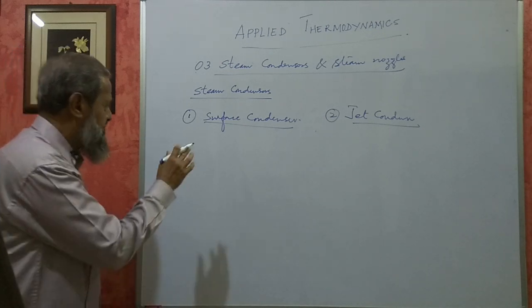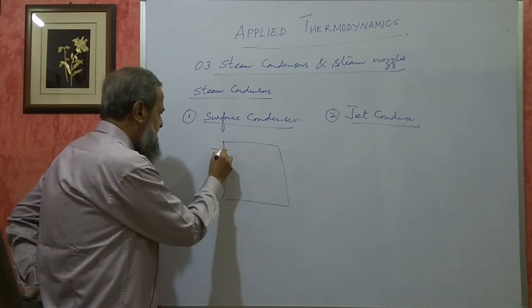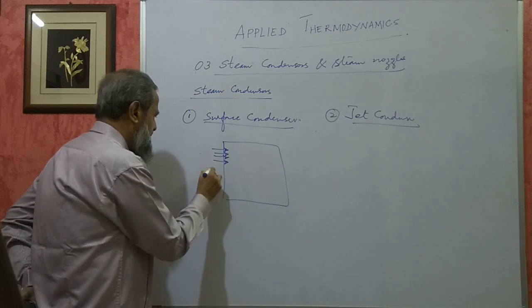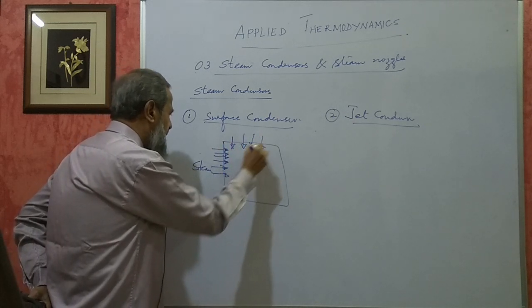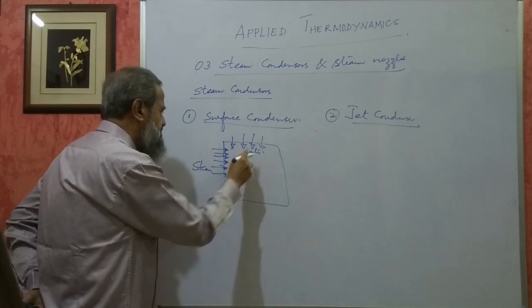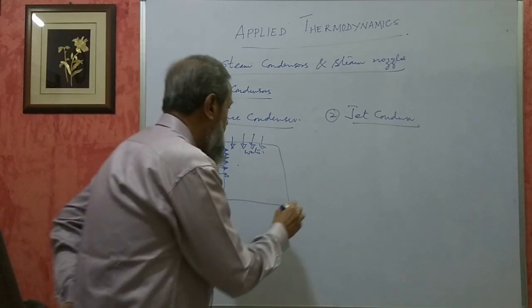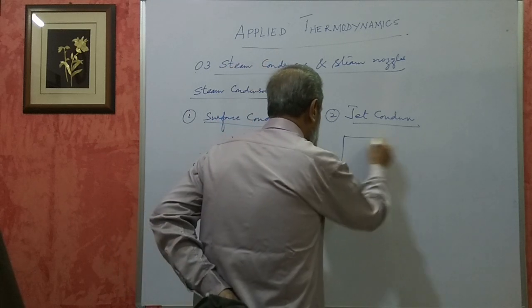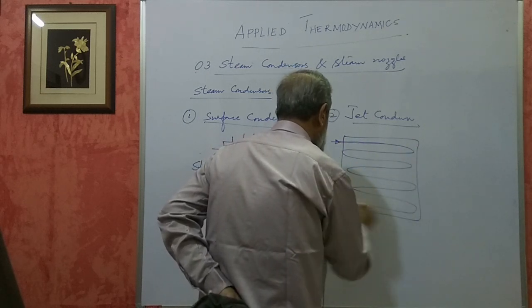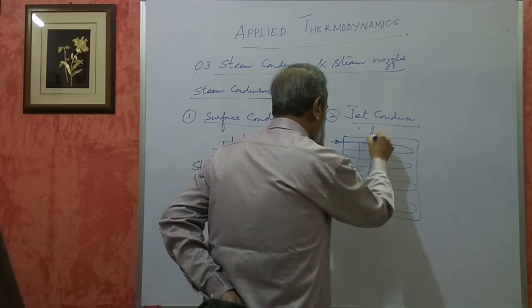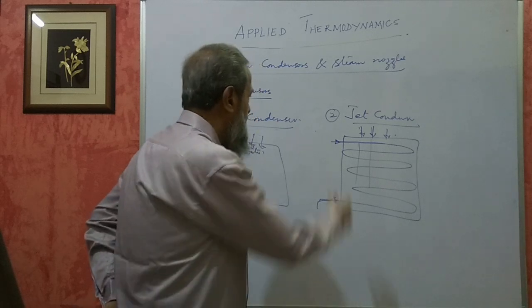The basic difference between the two is: in a jet condenser, it is a vessel maintained at vacuum pressure into which steam is discharged. Cooling water is also fed in. The cooling water and steam come in direct contact with each other - that condenser is called a jet condenser. In a surface condenser, the steam passes through pipes and cooling water is fed around them. They do not come in direct contact.